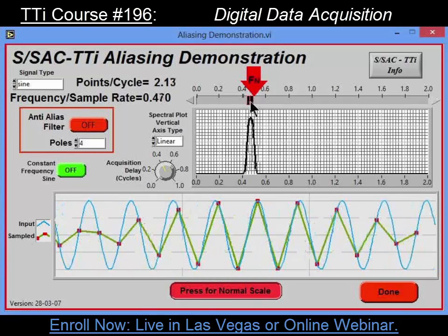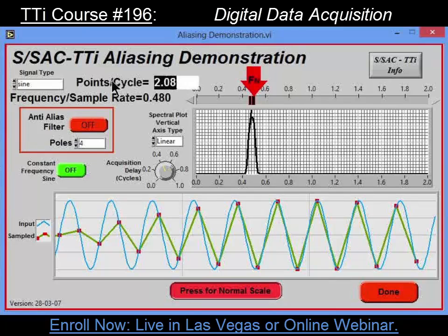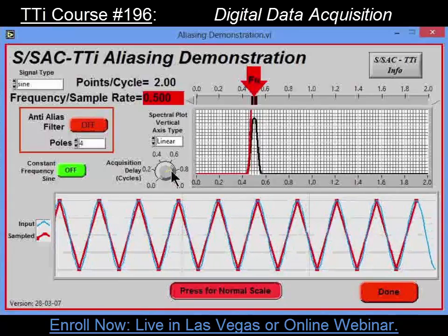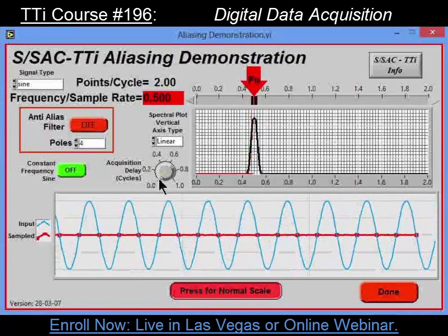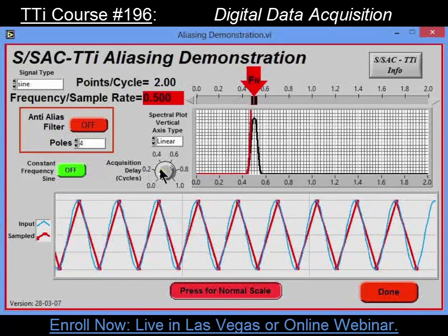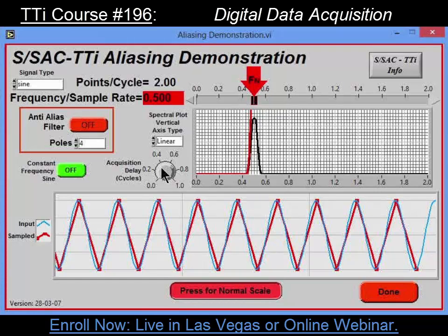Now I'm going to push on out until I am precisely at the Nyquist frequency. What I've got here is exactly 2 points per cycle, and this looks pretty good — it looks like I am representing the sine wave nicely. But the trouble is that I can get any answer I want by changing the time when I acquire the data during the cycle. If acquiring at one set of points, it looks like zero; at another set, it looks like full scale. Bottom line: I've violated Shannon's theorem and I've got an indeterminate answer.